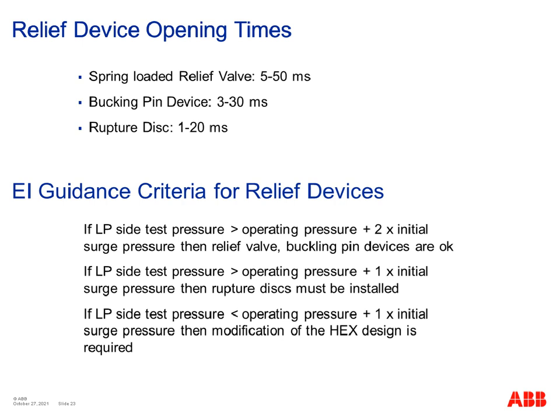So the EI guidance criteria for relief devices is as follows, and this is in the document that they've released. If the LP side of the exchanger test pressure is greater than the operating pressure of the LP side plus 2 times the initial surge pressure, and this is thinking about the surge pressure and the reflected surge pressure, that's why the 2 times comes into it. So if it's greater than that, then the relief valve and a buckling pin device is okay. If the LP side test pressure is only greater than the operating pressure plus 1 times the initial surge pressure, then instead of a relief valve or buckling pin device, you would need to have a rupture disc.